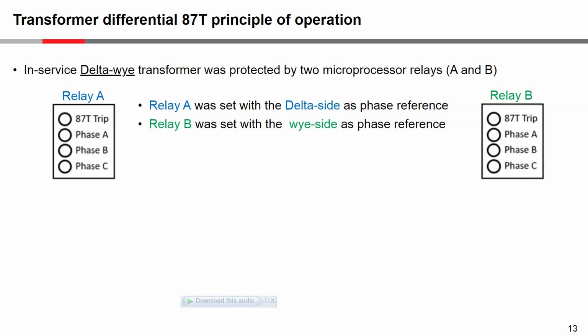So let's have a look here. Let's say we're protecting a transformer in service, and it has two microprocessor relays, A and B. Relay A is set with the delta side as the phase reference. As I said, it's a delta-Y transformer, and relay B is set with the Y side as phase reference.